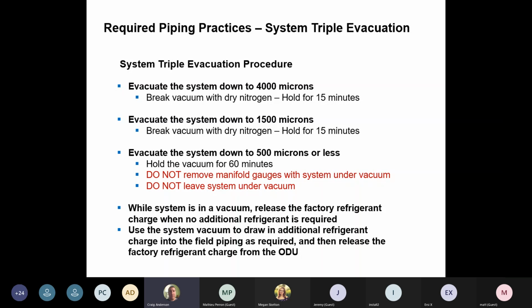So once you've done your evacuation, you've turned everything off, watch your micron gauge. It'll move up. Once it moves up, it should stabilize. And when we want it to stabilize, we want it to stabilize under 500 and we want it to hold there. If it doesn't hold there, then there's two things going on: you have moisture still in the line or you have a leak. Get it under 500, hold it there. We know we have the moisture out of the line.